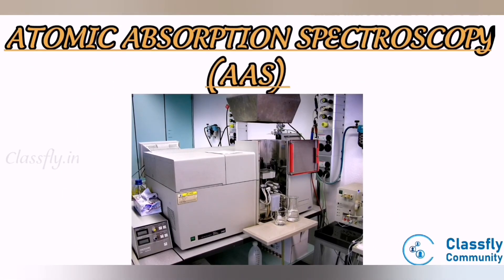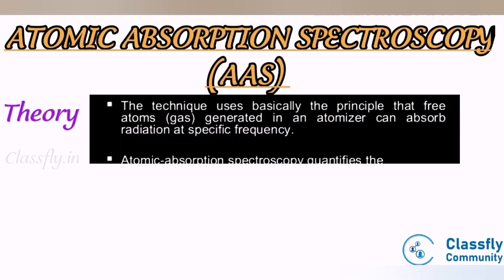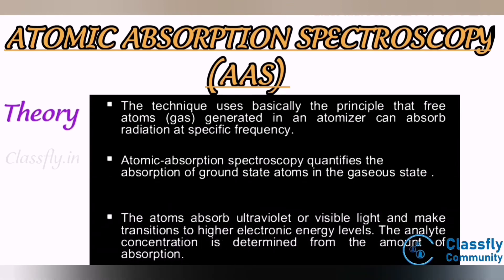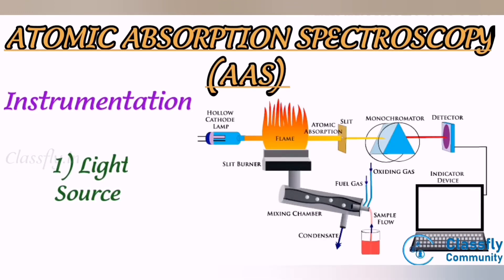Atomic absorption spectroscopy (AAS) is a very common technique for detecting metals and metalloids in a sample. It is reliable and simple to use, and can analyze over 62 elements. Theory: the technique is based on the principle that free atoms generated in an atomizer can absorb radiation at a specific frequency. AAS quantifies the absorption of ground state atoms in a gaseous state; the atoms absorb ultraviolet or visible light and transition to a higher electronic energy level.